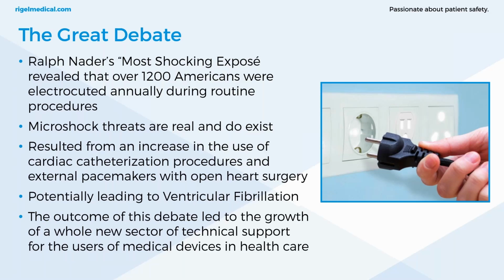Now, several years later after the exposé, the safety standard IEC 60601 was formed, and the revisions have led to year-on-year reductions in death from both macro and micro electrocution. And NFPA 99, which we're talking about today, is based upon that standard. So all of the electrical safety standards and performance standards originally derived from this exposé to prevent harm to patients within the biomedical engineering field. So it's led to a whole new sector for technical support and the users of medical devices in healthcare.